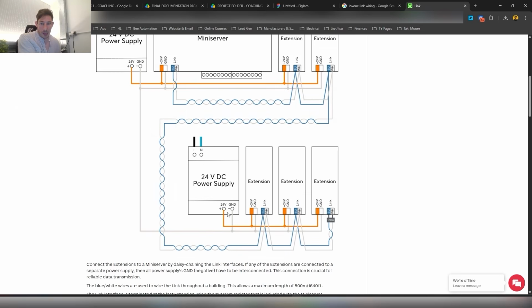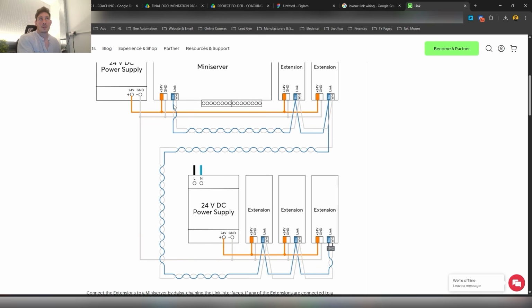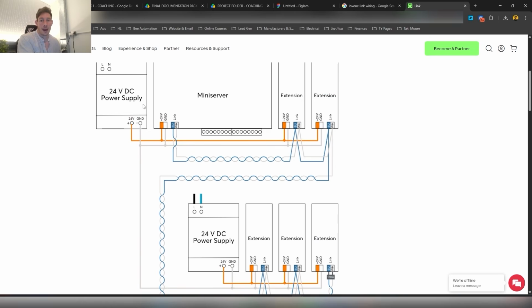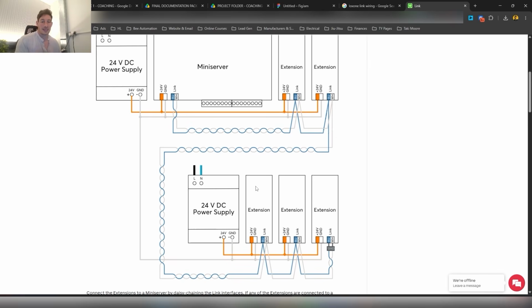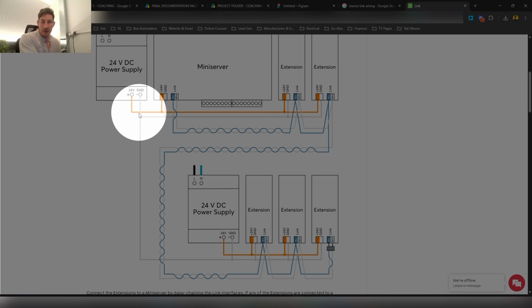And what can happen is if you don't common all of the power going to these extensions, without getting too technical, it can sometimes cause issues on the link where there's a potential difference. That potential difference, because the power across all these extensions isn't commoned, can then go onto the Loxone link, and that's obviously the communication to all of your extensions and controllers. That can then cause issues where you're not getting the communication you need from the mini server to the extensions to control things out in the field or whatever else. So that's why you always common the 0 volts of all your power supplies, to prevent things like that happening.